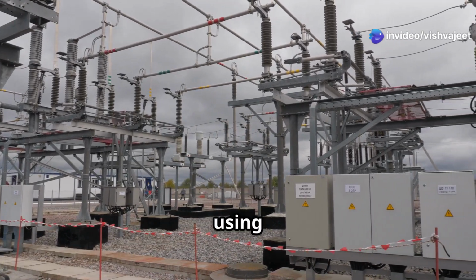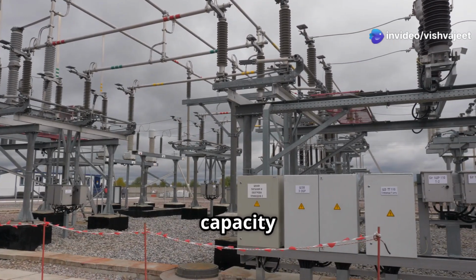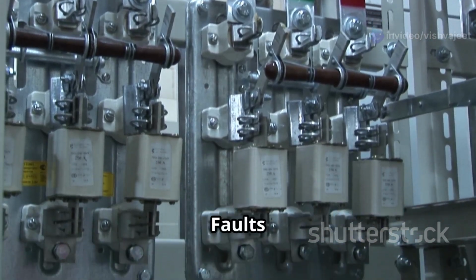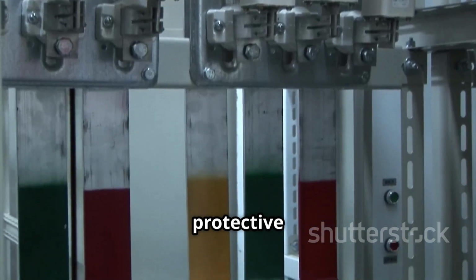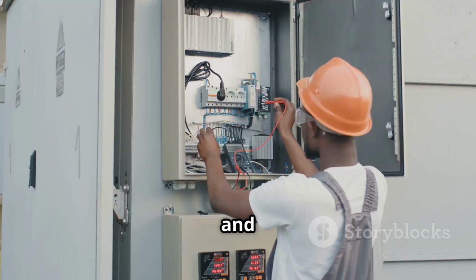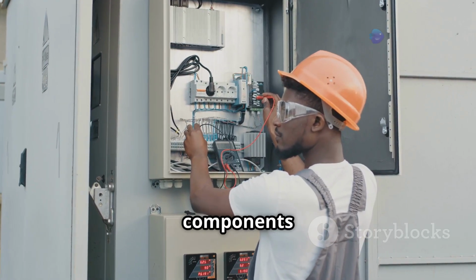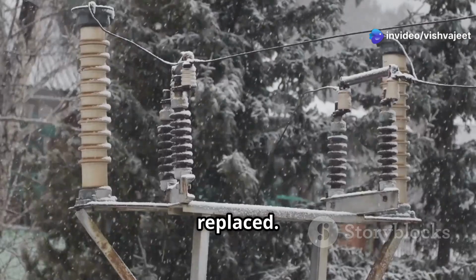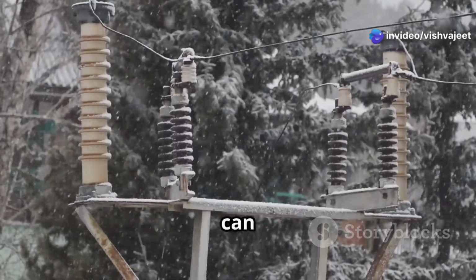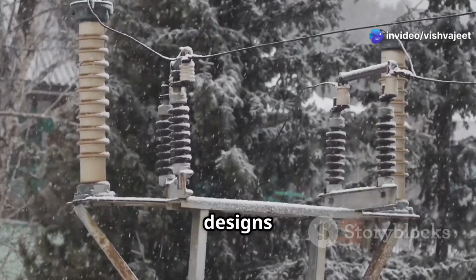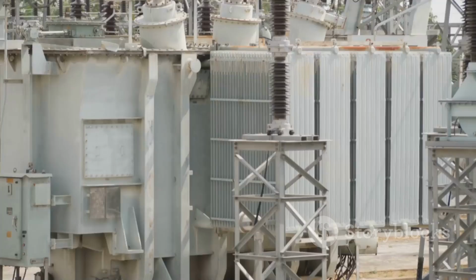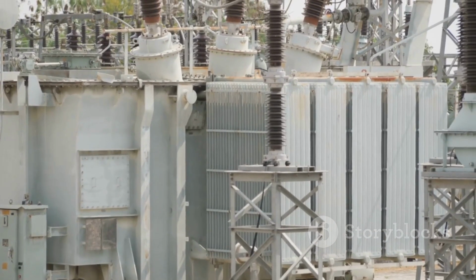Overloading can be managed by using transformers with adequate capacity and cooling systems. Faults can be addressed by installing protective devices like Buchholz relays and circuit breakers. Aging components should be regularly monitored and replaced. Environmental factors can be mitigated by using weatherproof designs for outdoor installations.